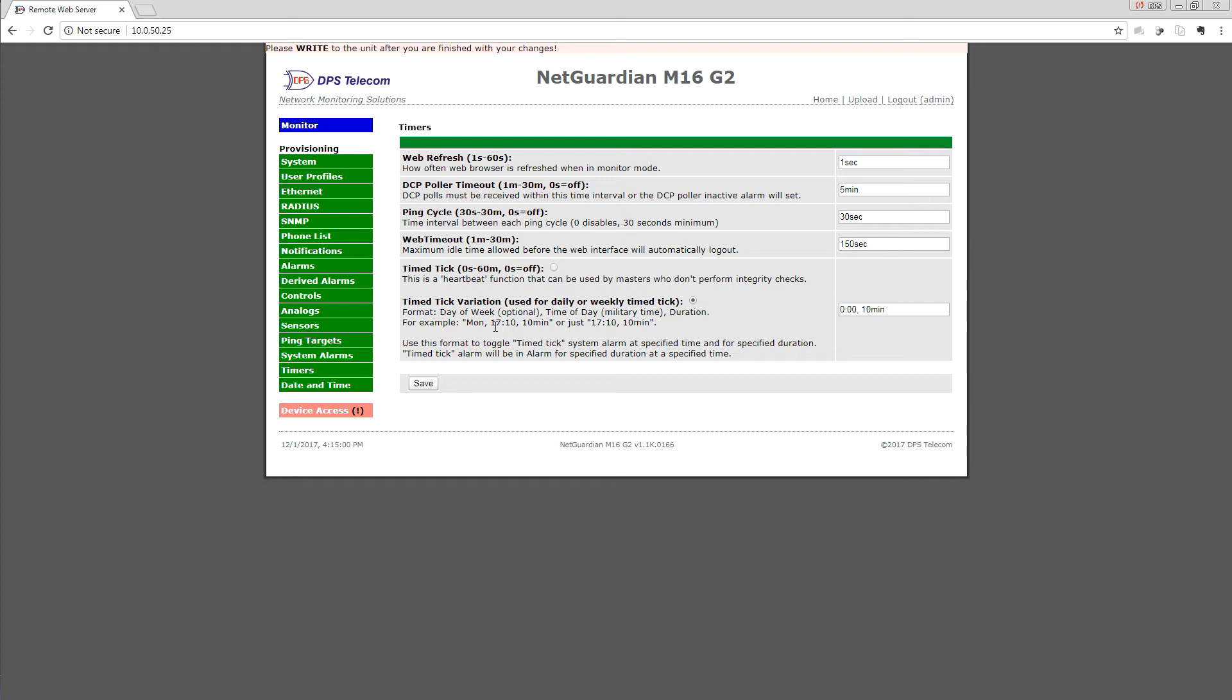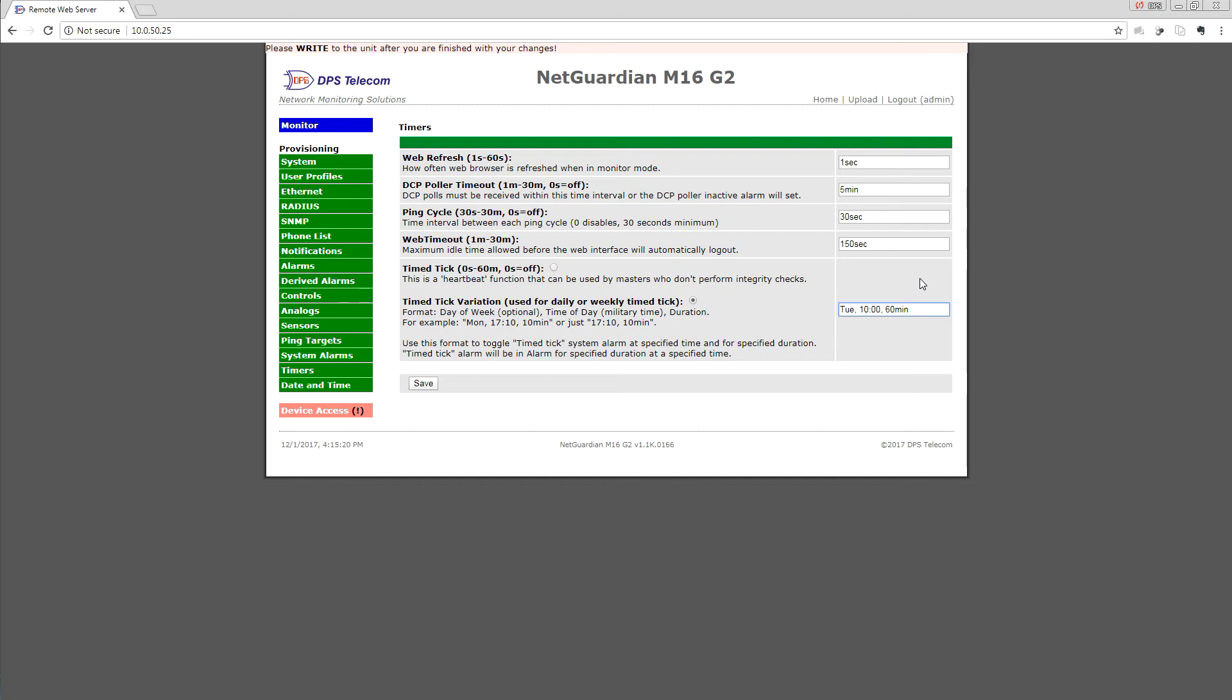That day of the week is what would correspond to our generator. So we want to say it's not actually Monday but rather Tuesday, and it's not 5:10 in the evening but 10 a.m. Our generator runs for 60 minutes. I will click Save here. Again, it's saved locally. We do need to write to the unit, but we have one last step to get this set up.